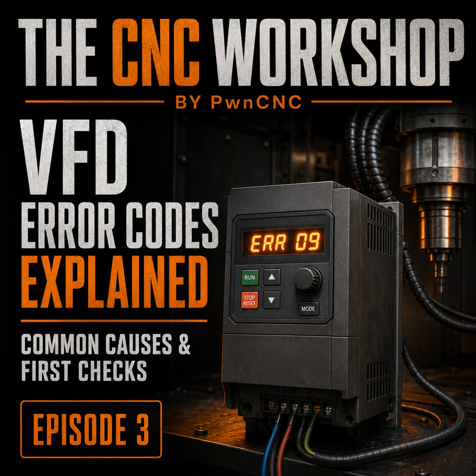Before we get into the individual errors, give us the quick version. What is the VFD actually doing when it throws a fault? The VFD controls the power going to the spindle motor. It is constantly watching electrical conditions such as current, voltage, and the balance of its output phases. When it detects something it cannot safely ignore, it may shut down to protect the VFD, the spindle, or both. So an error is annoying, but the VFD may be the only adult in the room at that moment. That's a fair way to put it.